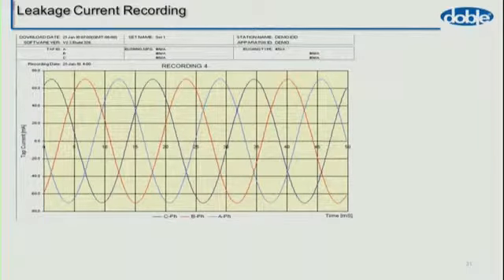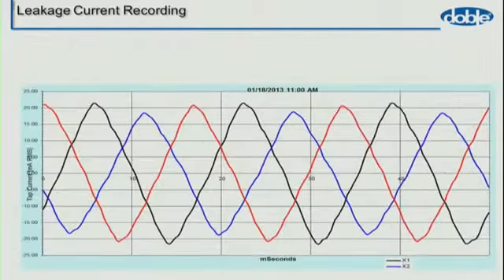Unfortunately, it doesn't matter how well you control the actual measurement, in reality it's not like that. You have to understand the context. The system voltage changes, bushings may not be the same, they have different capacitances. These are real leakage currents, and those leakage currents are not sinusoids, they're not equal magnitude, and they're not 120 degrees apart. But this is what you have to get used to.